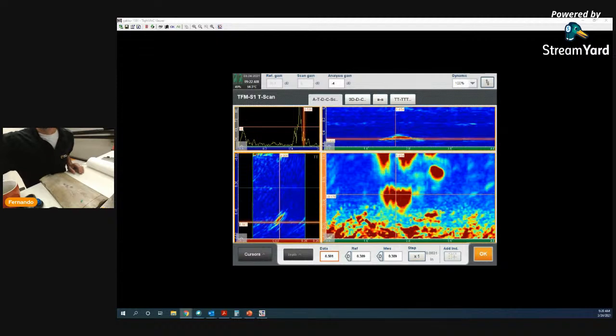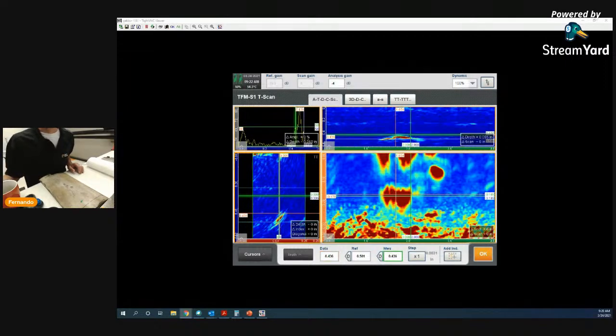So we'll go depth. I know the indication starts at the top, so I can put a reference cursor there and then peak it out about right there. Hit measure, and on the screen it tells me the depth up here on the A-scan. You can barely see it, but the depth is going to be 0.065. This is a real life sample, right? We scanned it with the other equipment, and it coincided with the height. So they all work together.